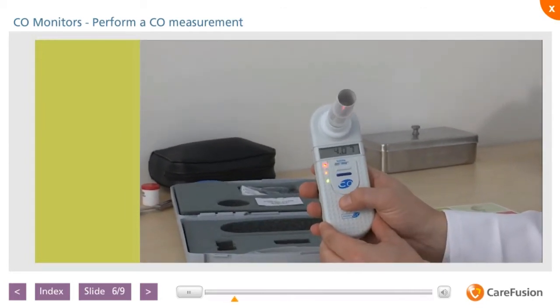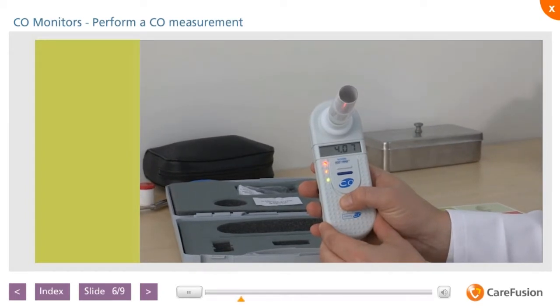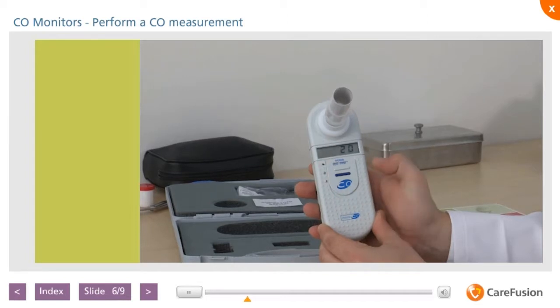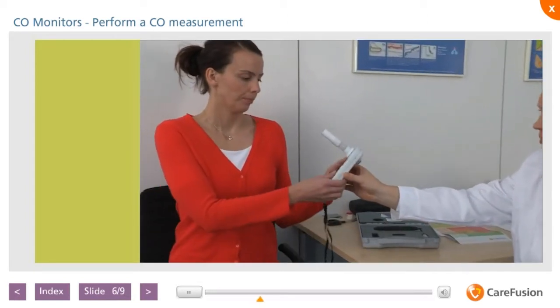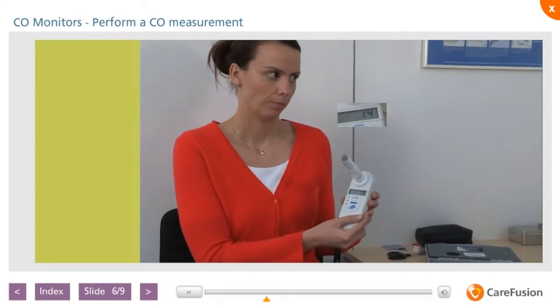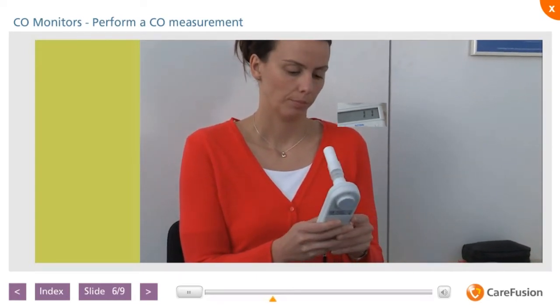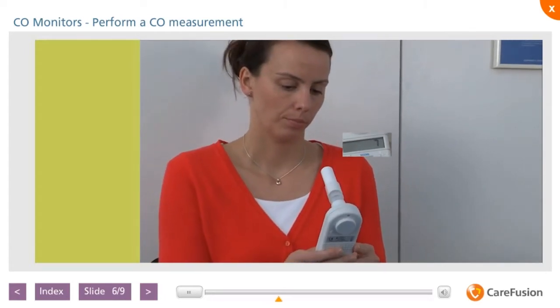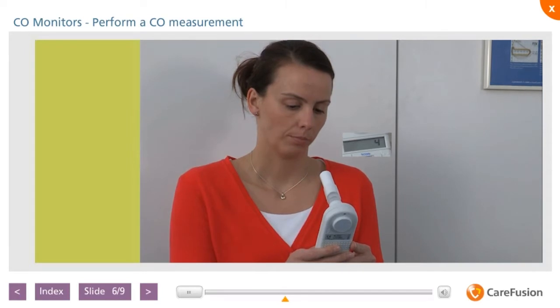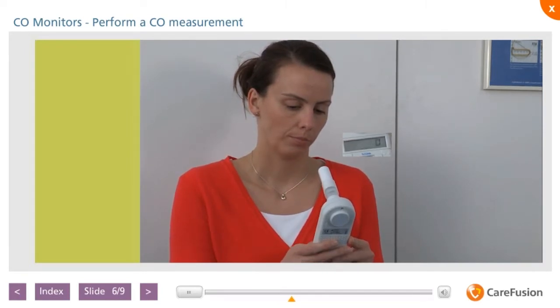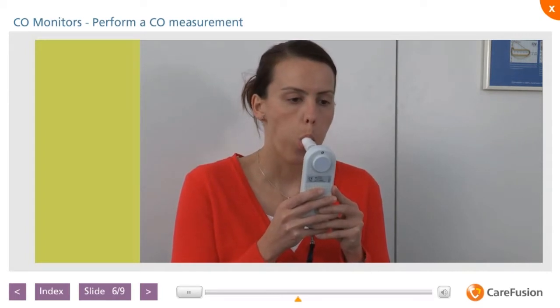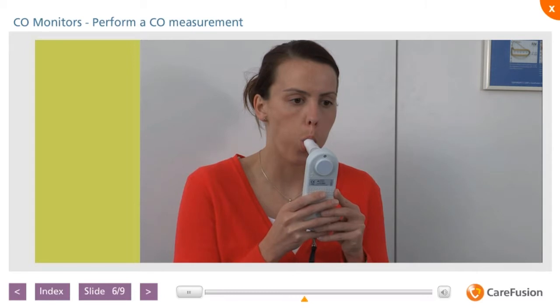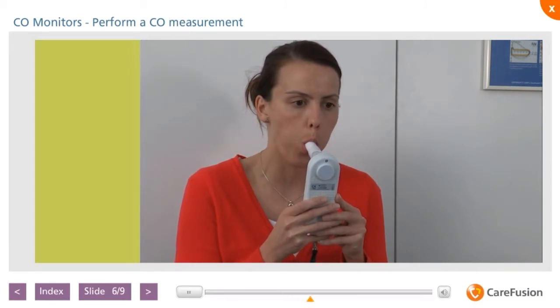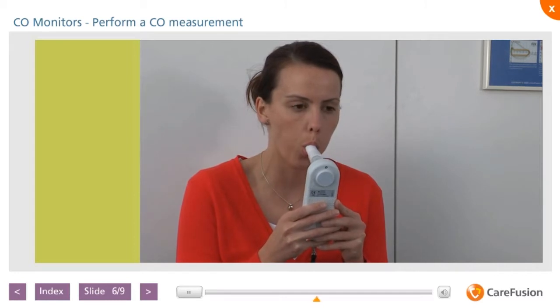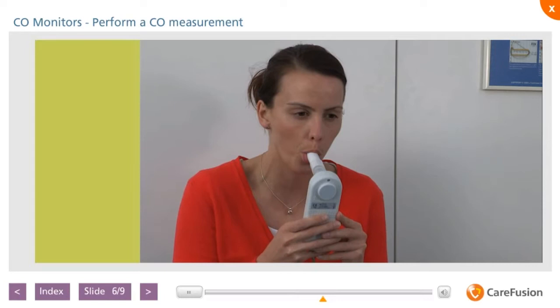To switch the unit on, slide the switch to the parts per million position. The software version number appears, immediately after which a down counter will appear for 20 seconds. At this point, the patient should inhale as deeply as they can and hold their breath as long as possible. The breath-holding period is recommended to allow time for the resulting alveolar gas to equilibrate. If the patient is unable to hold his or her breath up to the point the 0 appears on the display, the test may still be carried out. Ask the patient to place the mouthpiece in their mouth and exhale at a sustained and comfortable speed until they feel they can exhale no further. It's important you encourage the patient to keep exhaling for as long as possible.